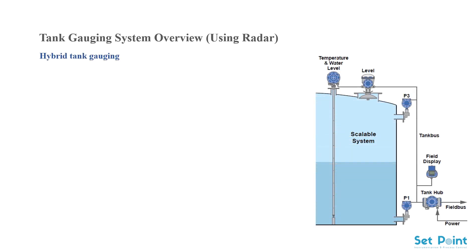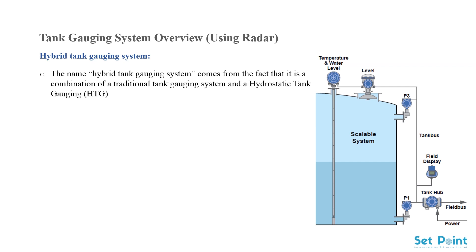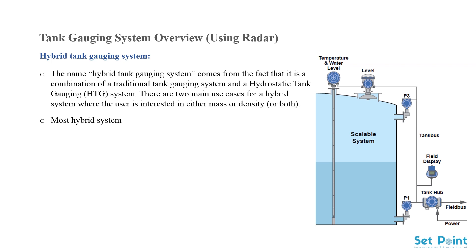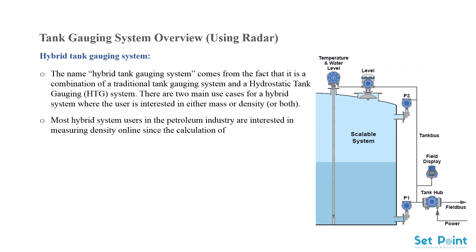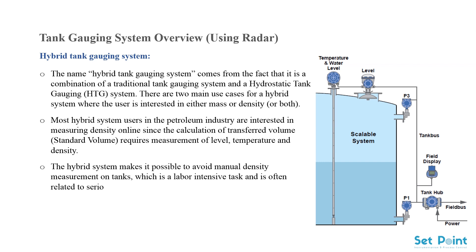The hybrid tank gauging system gets its name from the fact that it is a combination of a traditional tank gauging system and a hydrostatic tank gauging (HTG) system. There are two main use cases: where the user is interested in mass, density, or both. Most hybrid system users in the petroleum industry are interested in measuring density online, since calculating standard volume requires measurement of level, temperature, and density. The hybrid system avoids labor-intensive manual density measurements, which are often prone to serious errors if not done properly.